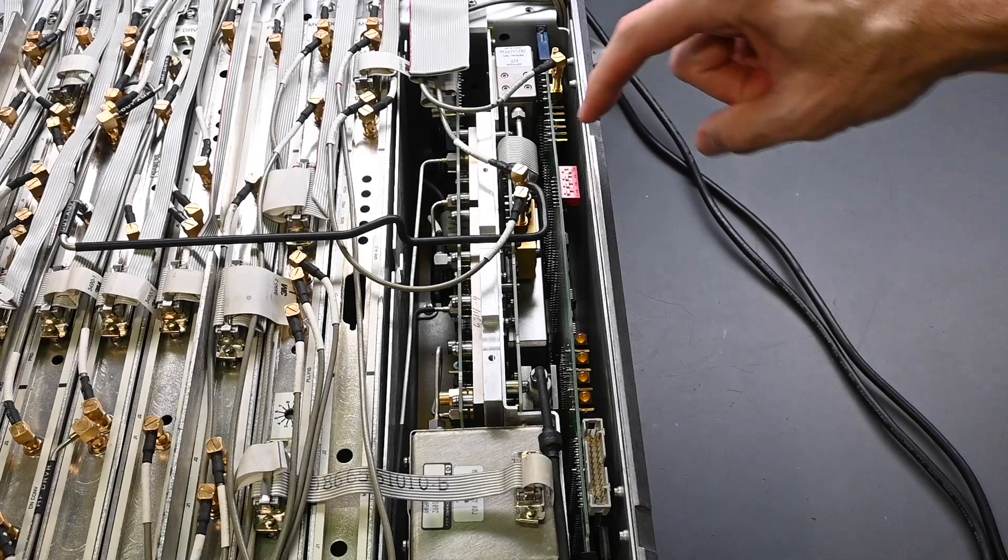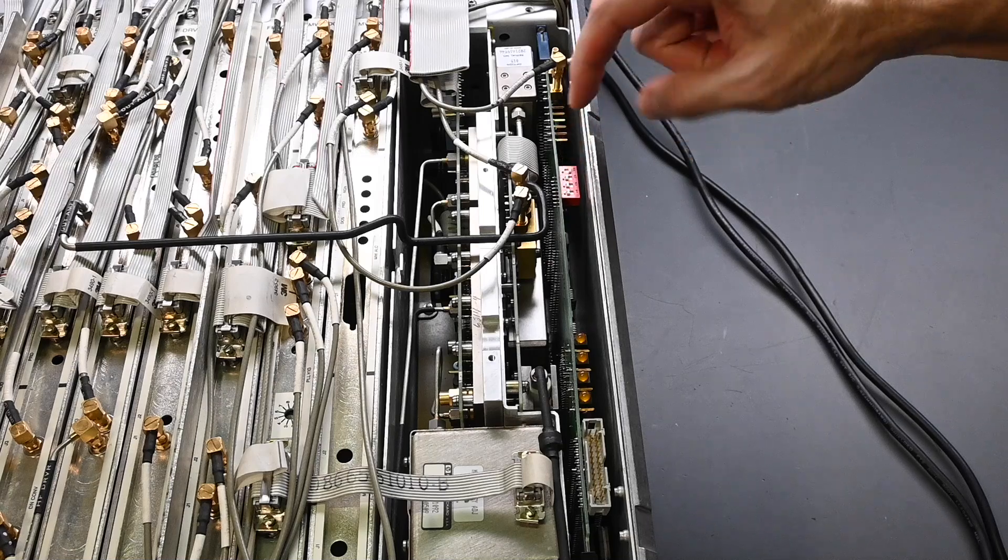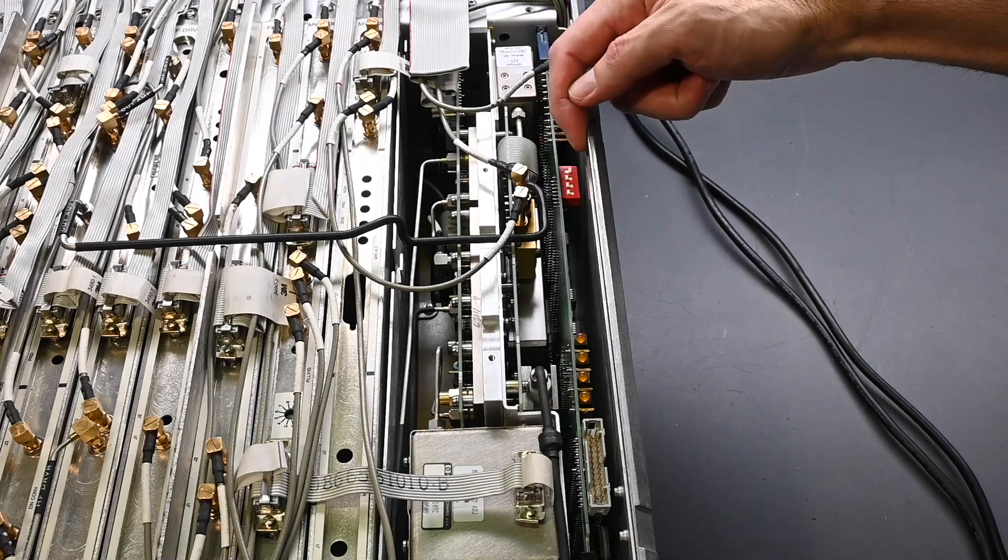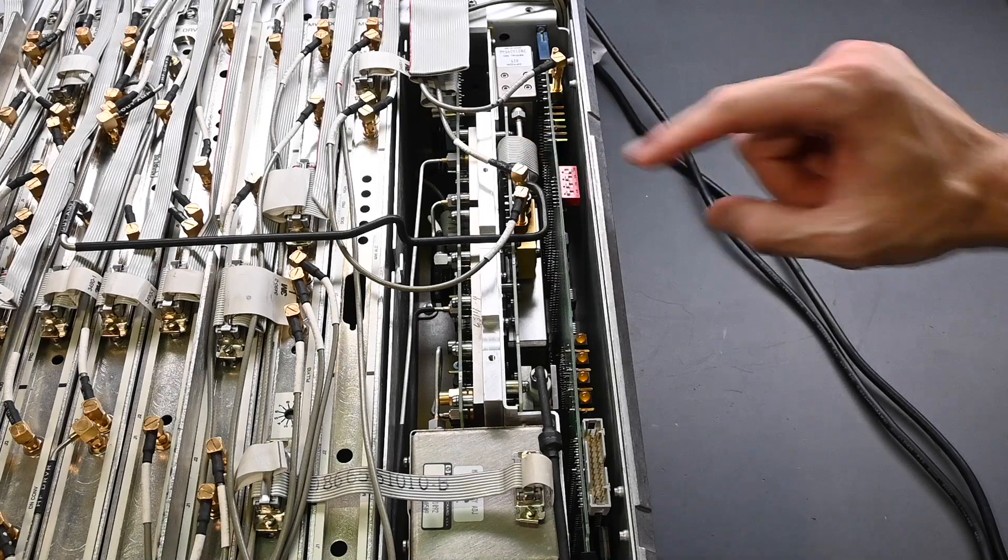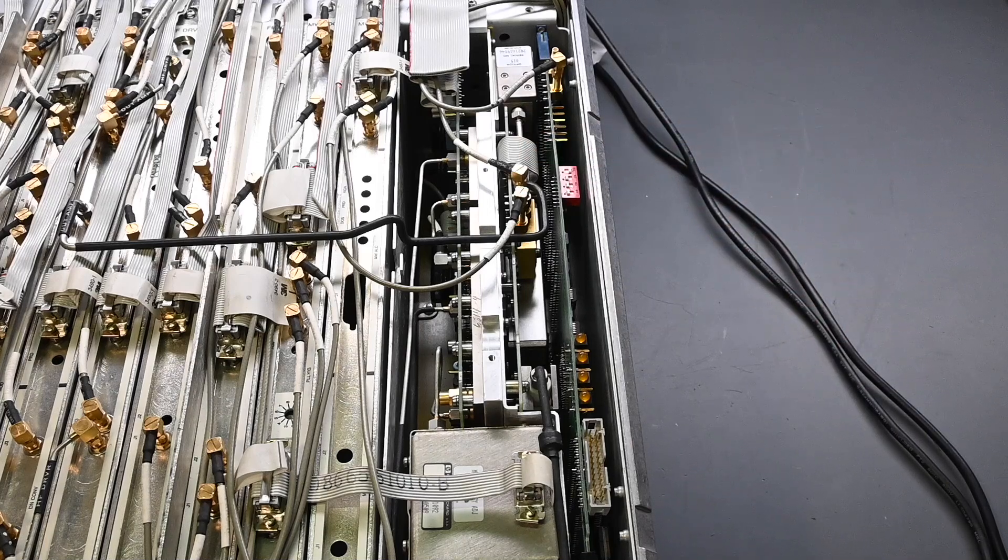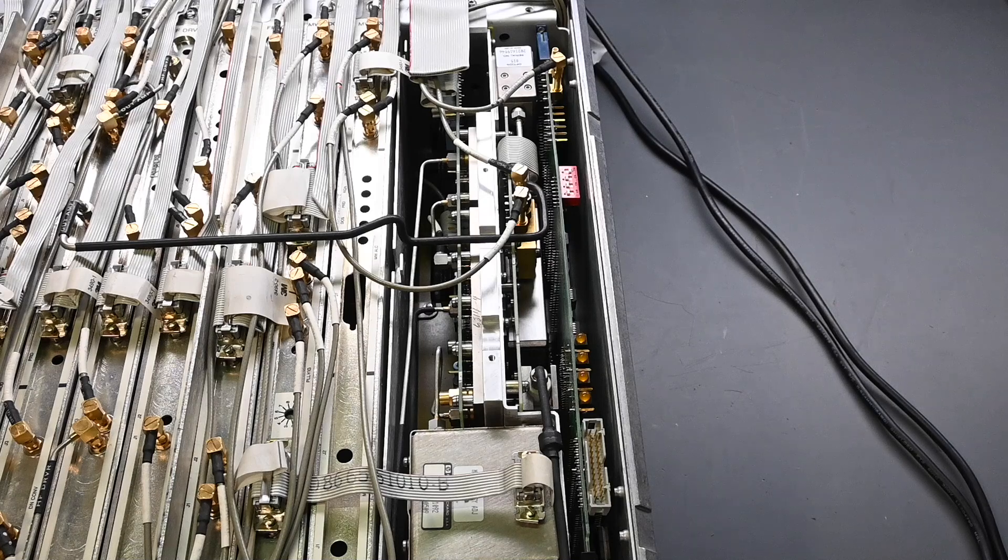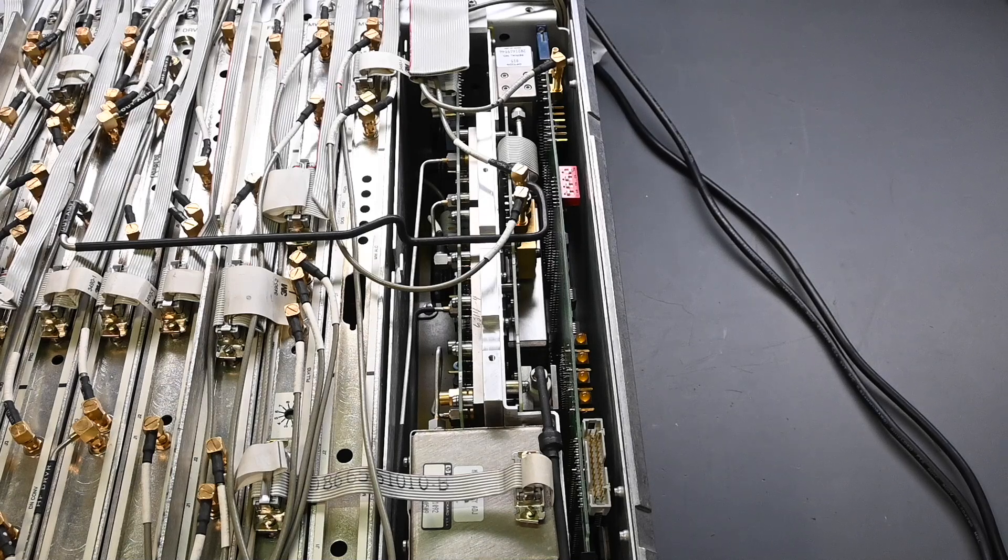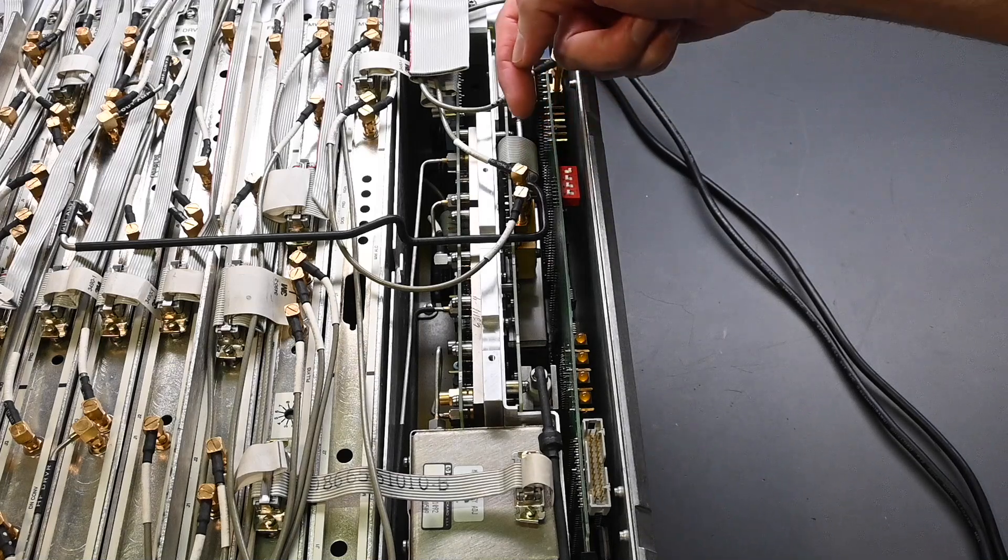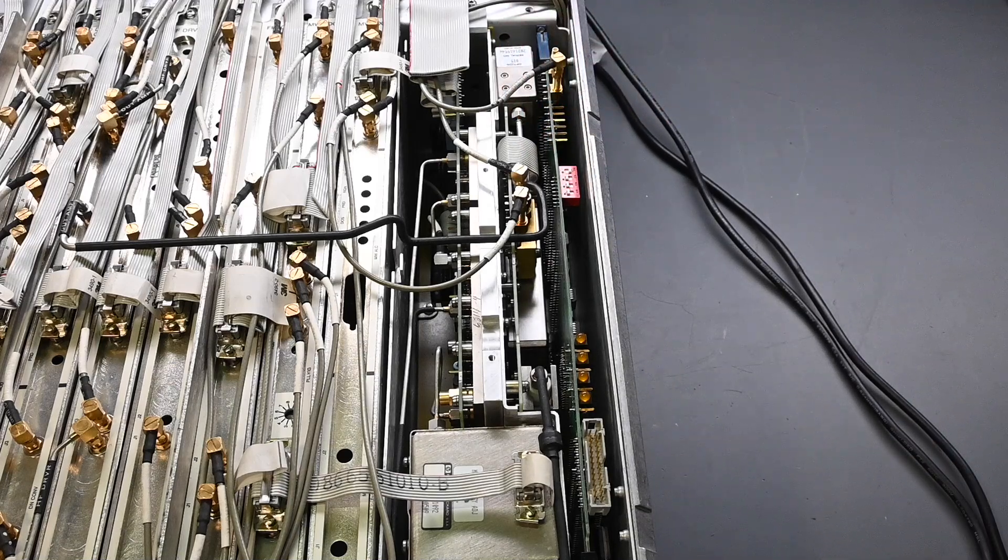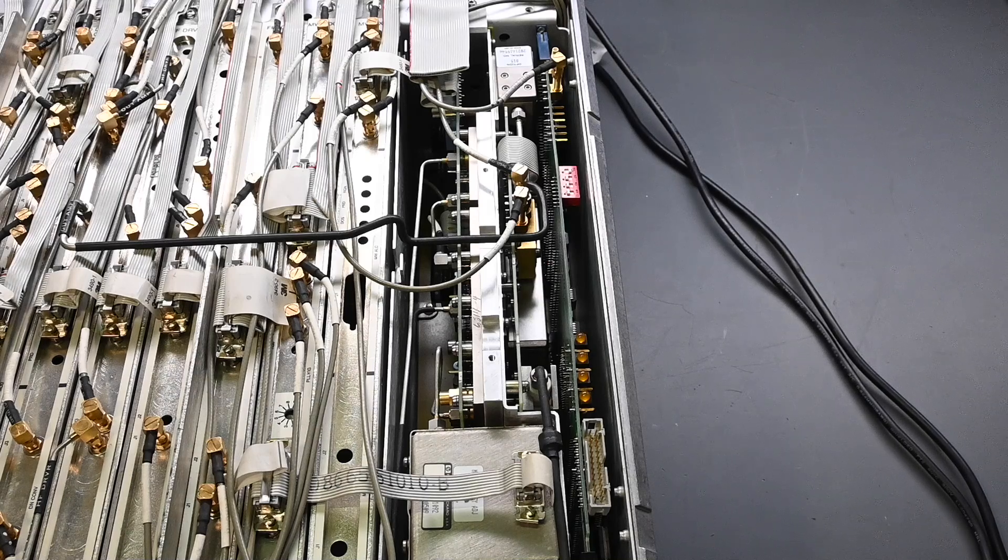Now take a look right here, these four switches right there, notice the first switch is to the outside direction of the instrument, and the other three switches are that direction. So to access those 300 level service menus, so the 306 and the 304, and there are many other service menus as well, but to access anything in that 300 level, this first switch needs to be this outside direction, so keep that in mind if you're working on one of these instruments, and you need to get to those service menus.